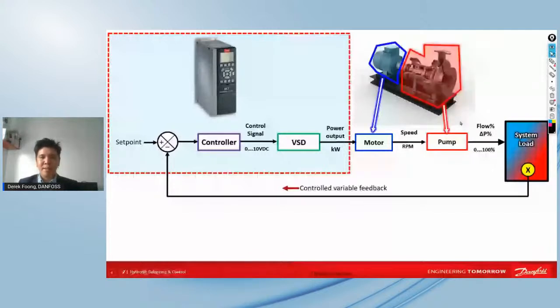So after that, the pump will primarily give the output of pressure, or differential pressure in this case, and the flow at the same time to the system load. All right, so the process goes back, X is the pressure point in the system, and this is where it takes the feedback as an analog input to the summing junction. The summing junction is where the set point and the feedback are always compared, and it sends the error to the controller so that it can process the differences and decide what signal is supposed to be given to the drive to modulate the motor.